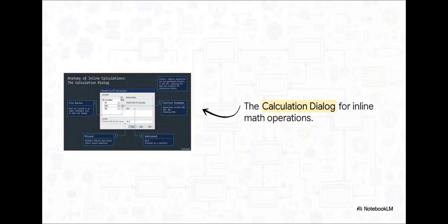In the past, if you needed to do some simple math, like say subtracting 10 degrees from a baseline temperature before triggering a transition, you had to build all these messy external calculation blocks. Well, not anymore. Inline calculations let you perform mathematical operations directly inside the SFC. It keeps your entire workspace incredibly clean and perfectly contained.